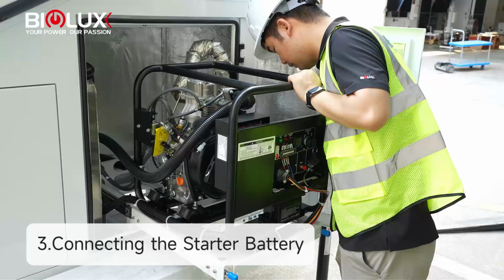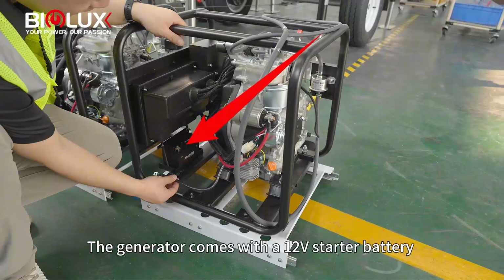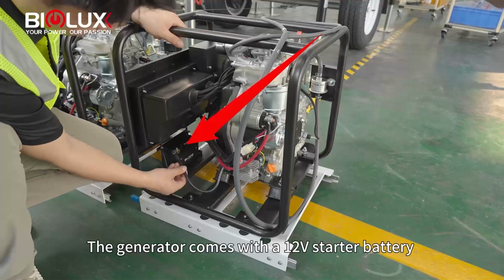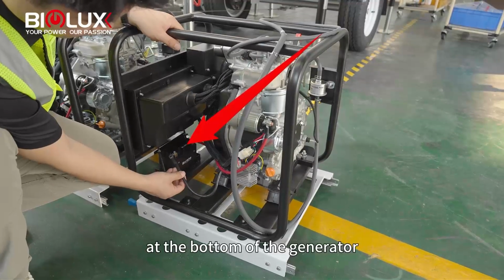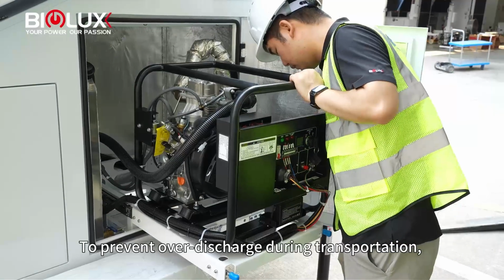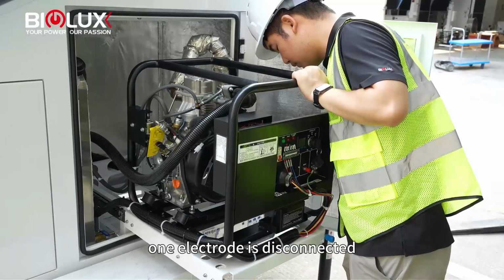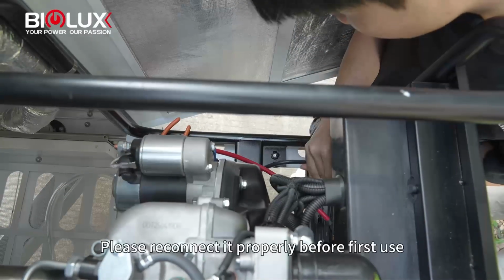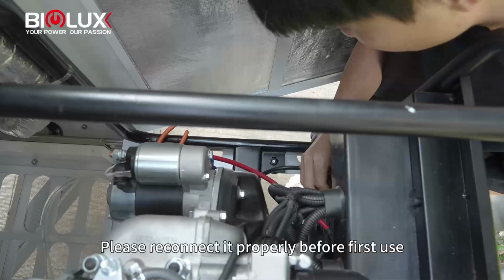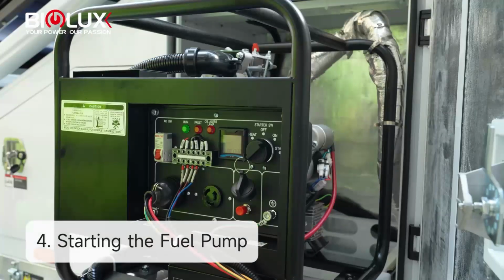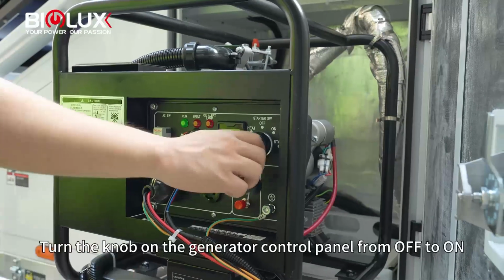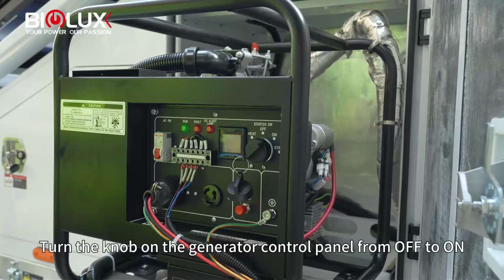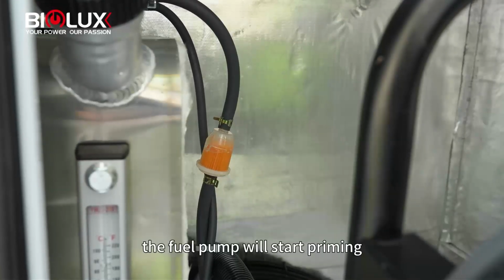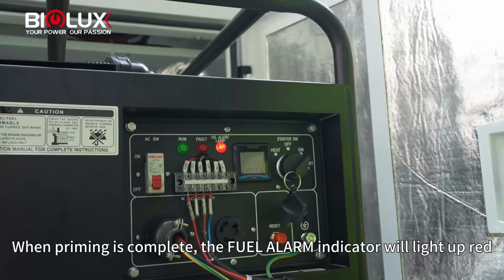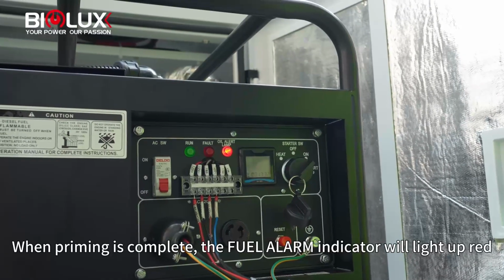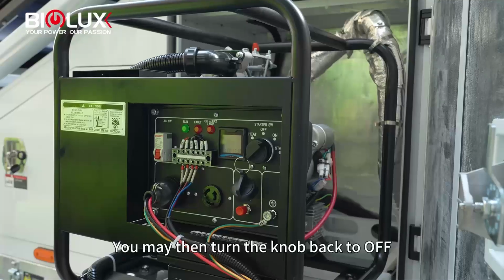3. Connecting the starter battery. The generator comes with a 12-volt starter battery at the bottom of the generator. To prevent over-discharge during transportation, one electrode is disconnected. Please reconnect it properly before first use. 4. Starting the fuel pump. Turn the knob on the generator control panel from off to on. The fuel pump will start priming. When priming is complete, the fuel alarm indicator will light up red. You may then turn the knob back to off.